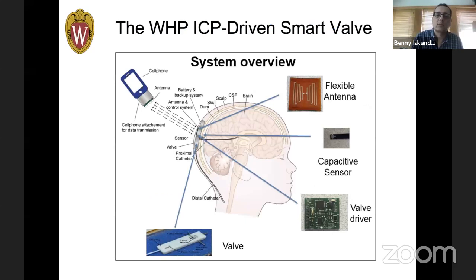And this is the valve system that we've developed. It has an ICP sensor with a flexible antenna. It has a valve driver, a bunch of electronics that takes the ICP, averages it, and sends it to the valve. And this is an on-off valve, which opens only when the driver tells it to open. The whole thing is controlled by your cell phone, by an RFID device, and the battery is charged by the same mechanism. You can imagine an RFID device a meter or two away, maybe on a pillow at night or at your bedside table, that recharges the valve overnight.